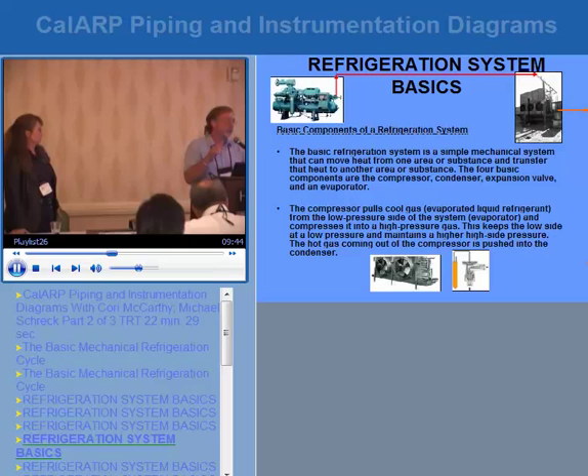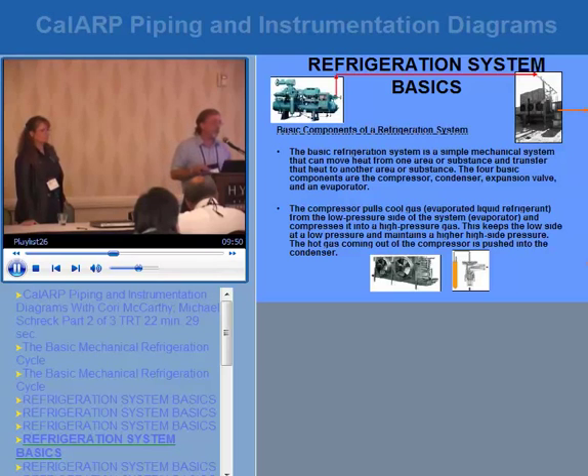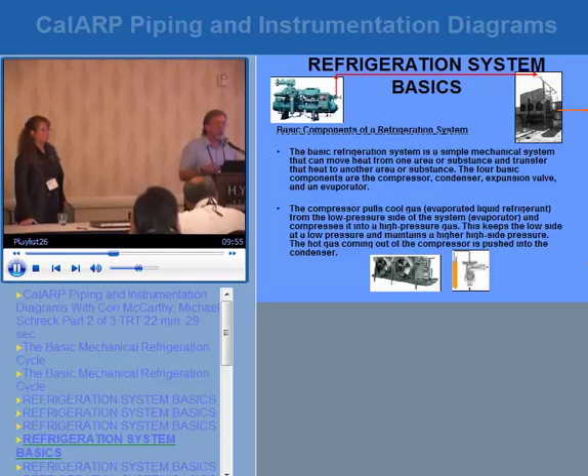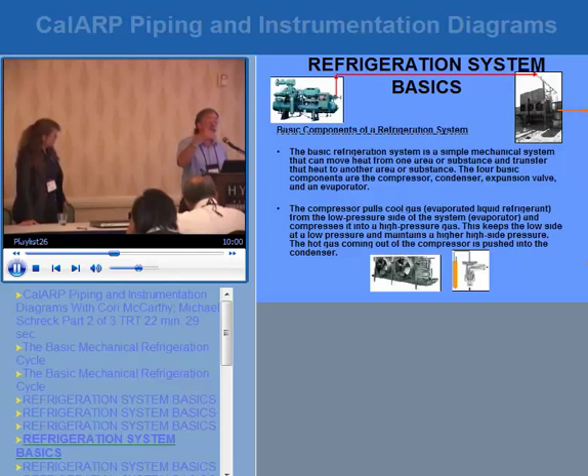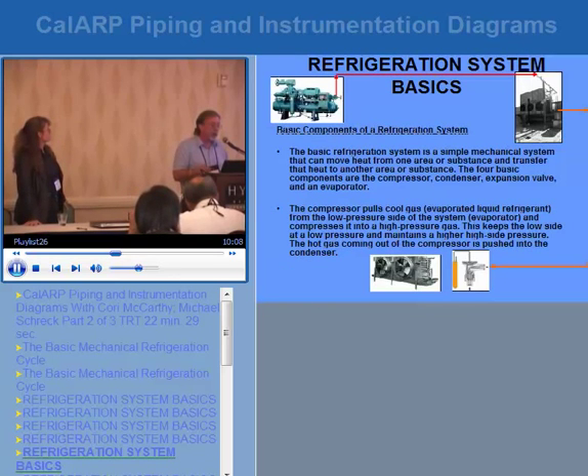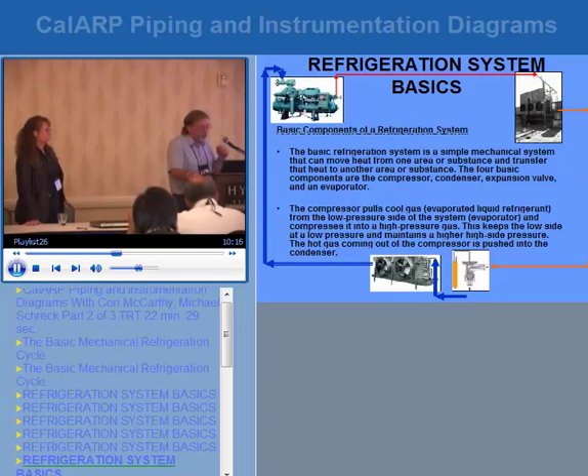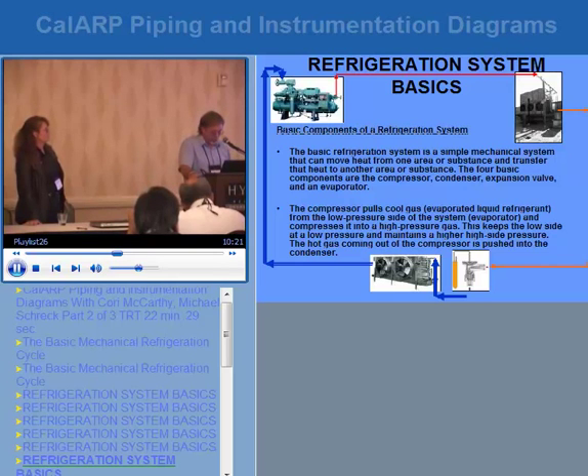In the engine room we have a lot of control — we have ventilation, ammonia detection, diffusion, and other safeties. Out in the rooms we typically don't have those options. From the evaporators, we pick up the heat, expand the refrigerant, push it into the compressor, and the whole cycle starts over again. You need to know the basic flow of refrigerant, and you can do that by looking at the P&IDs — they'll have directional flow on them, and hopefully the pipes are labeled in the plant as well.